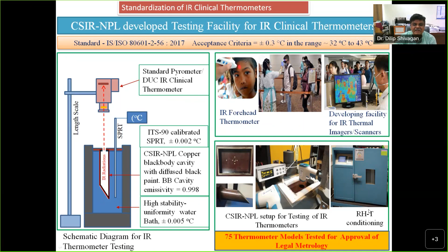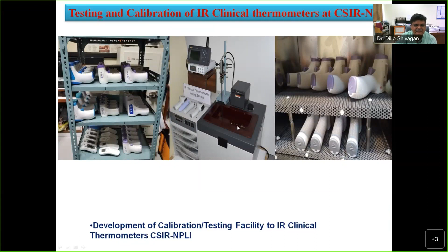So such a critical cavity black body was required. It is kept in a very highly stable bath, 0.005, and the thermometer was calibrated at a fixed point. All this constituted the radiation black body being properly characterized. This was used for the climatic condition changes, so our primary standard of humidity was used directly for this purpose. All focus was on this work, and as you can see, several models and how they are characterized in the climatic chamber. So this facility we have developed.